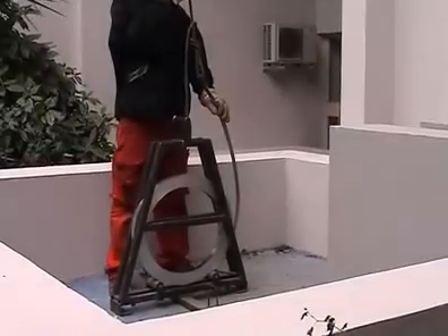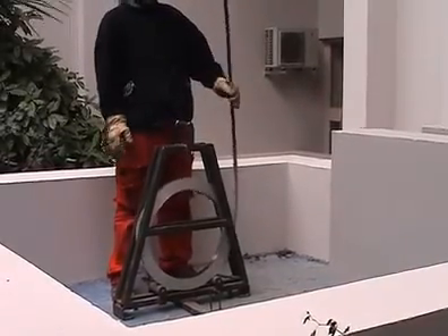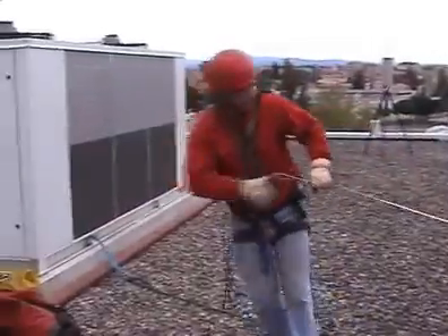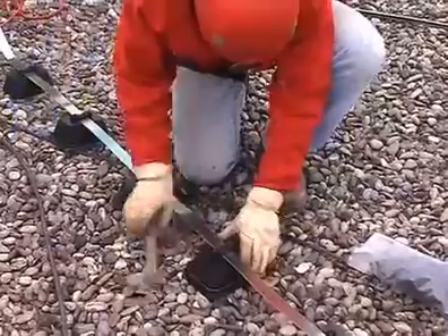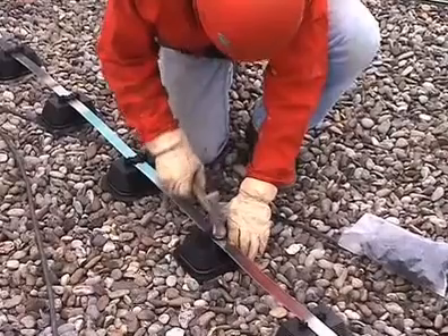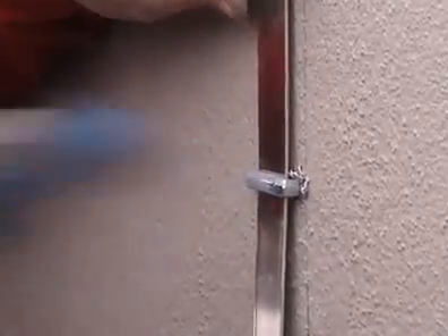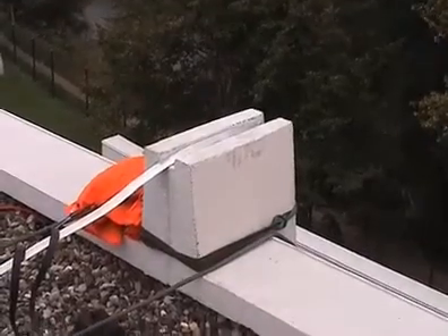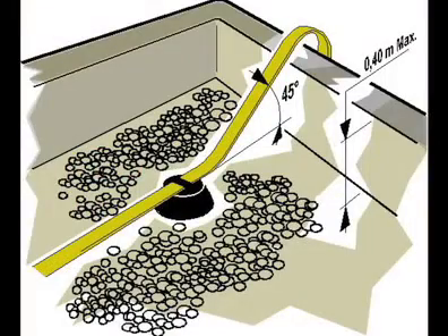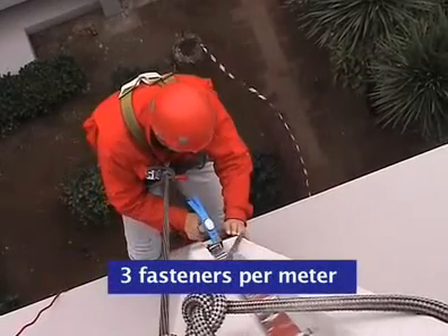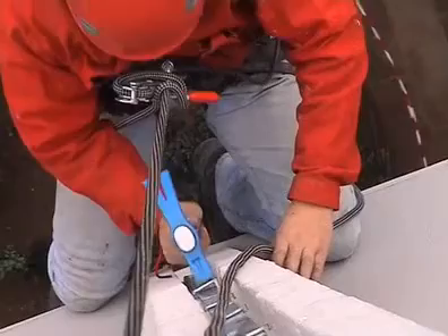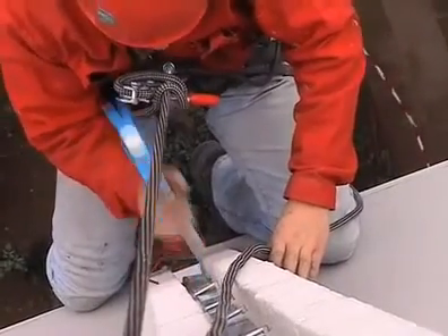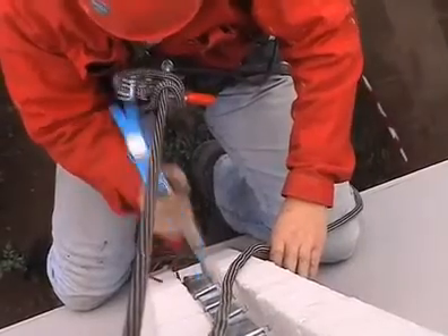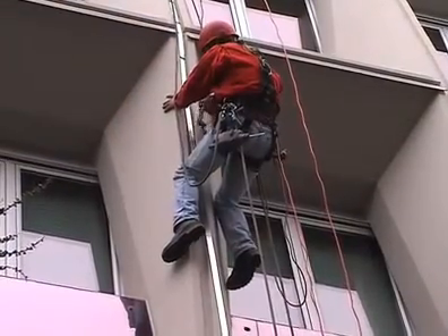We now use a rope connected to a tape drive to position the flat conductor on the roof. Install the roof fixing accessories, 3 per meter. Clip the tape onto the studs fixing accessories and the wall. To route it over the parapet, the following bending shapes need to be achieved. Fit the tape onto the wall using 3 fasteners per meter. These operations must be carried out by an approved installer according to the strict rules of security.